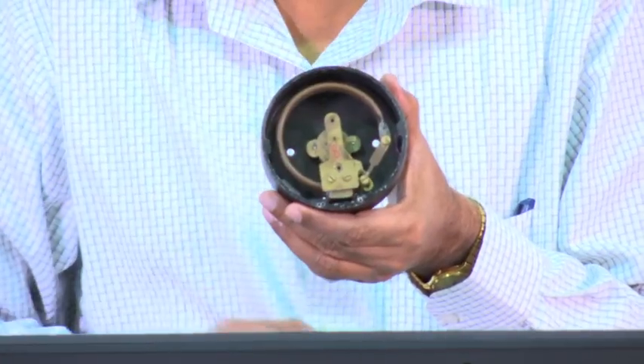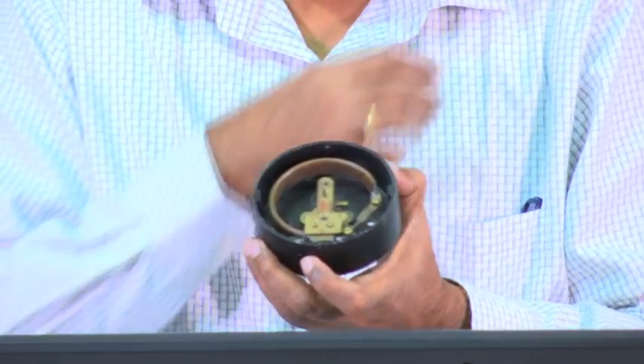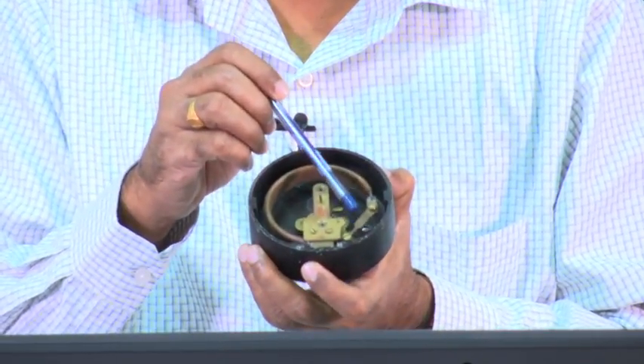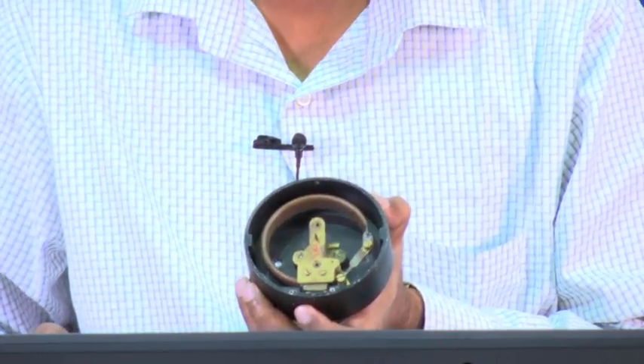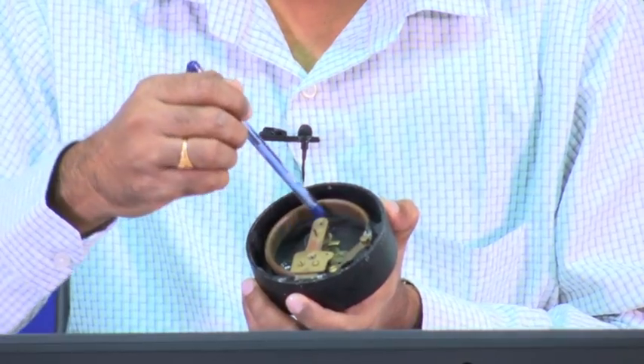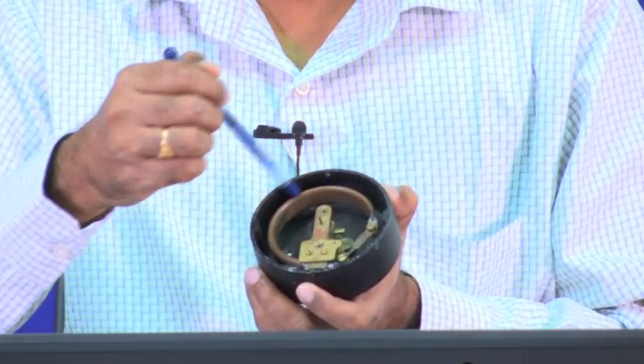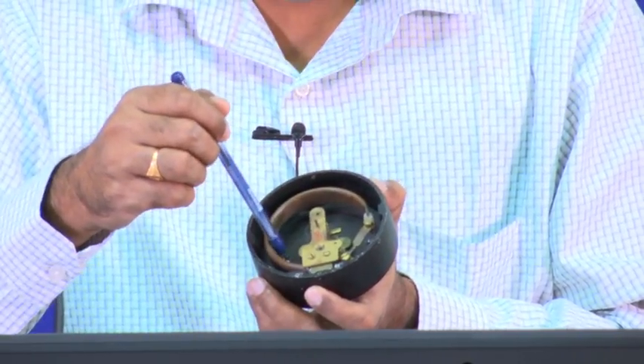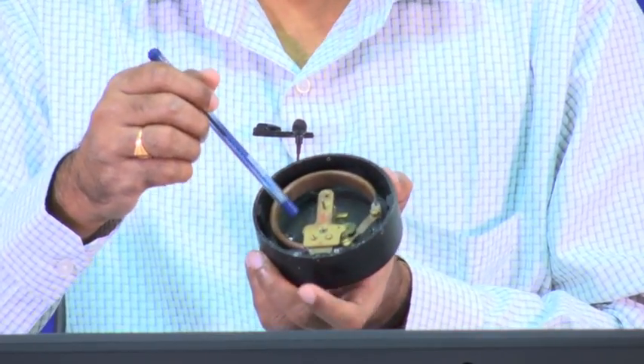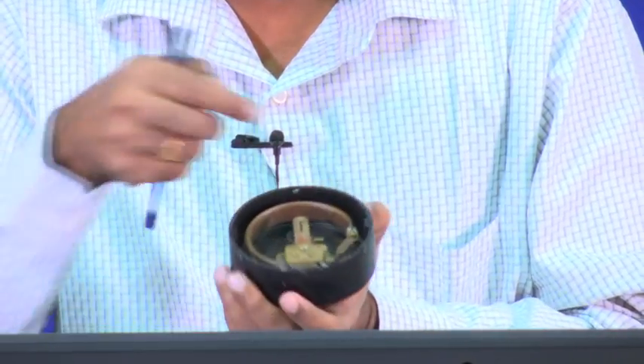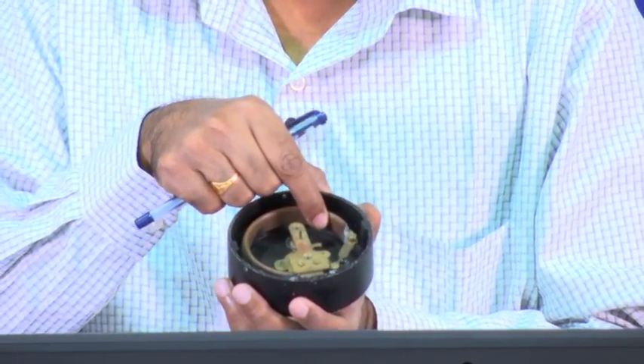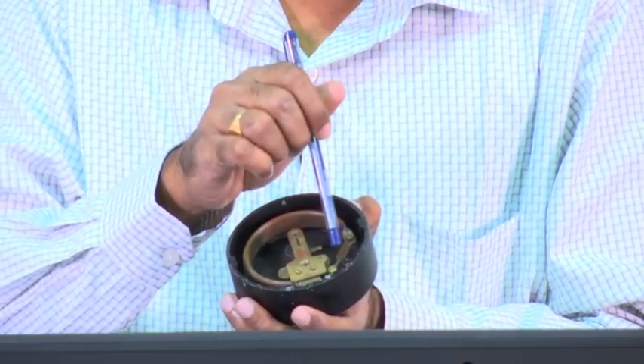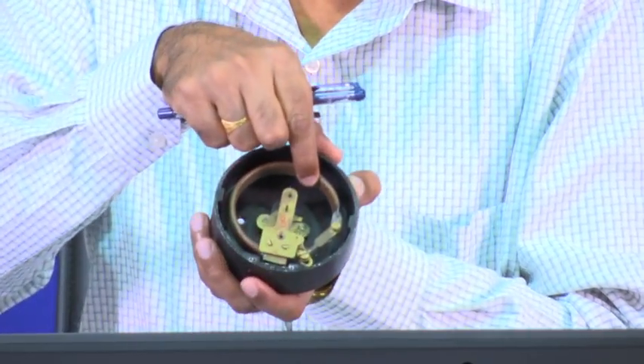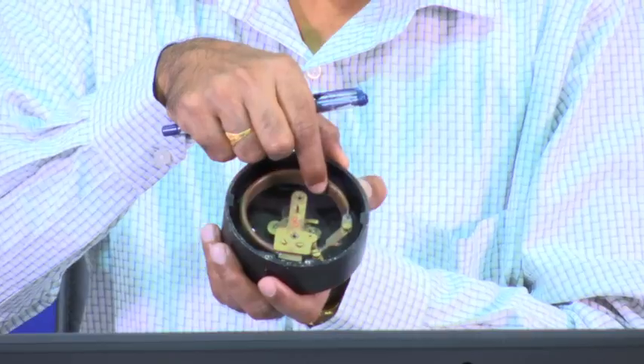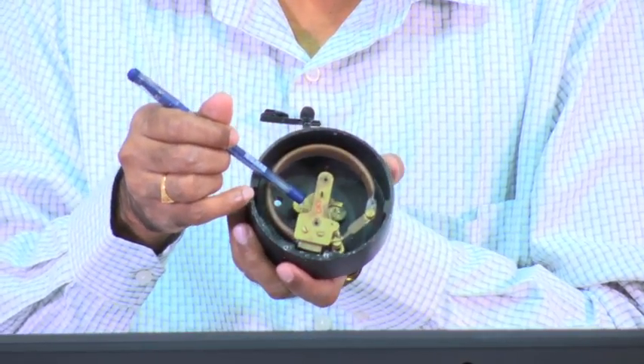Now, look here. This is the link, and you can see that the cross section of this Bourdon tube is elliptical. It was originally circular, then they flattened it to give it an elliptical shape. When you apply pressure here, this tries to straighten up, and as it does, you see this lever, the sector pinion assembly, all of these move. And look here, this is the hairspring that I was talking about.